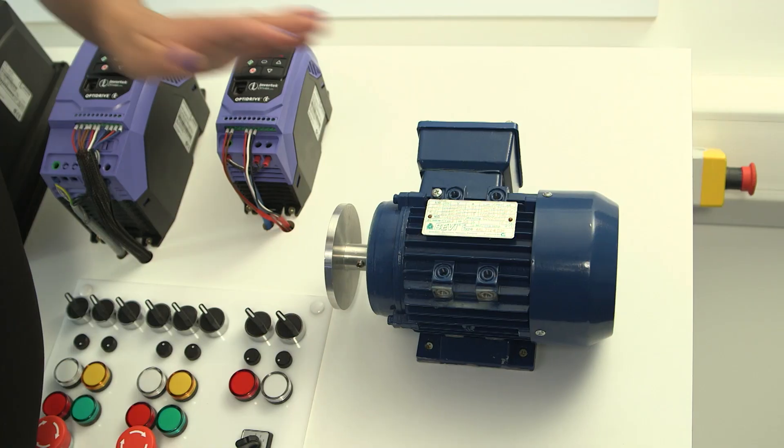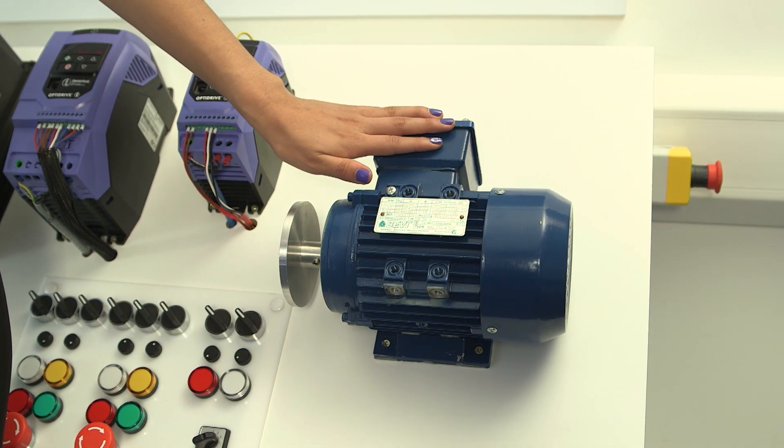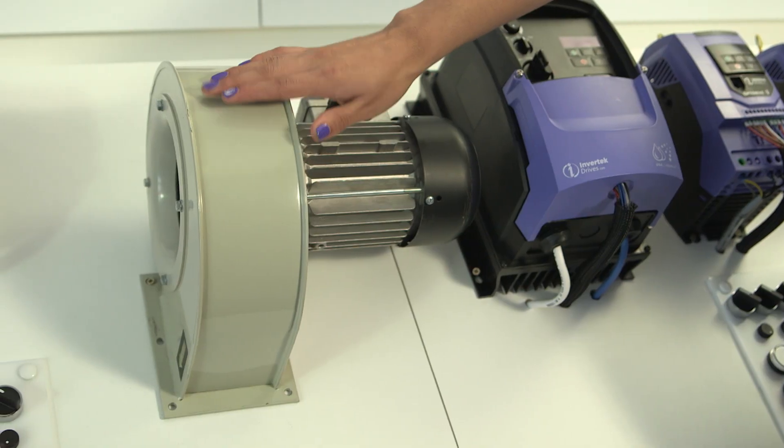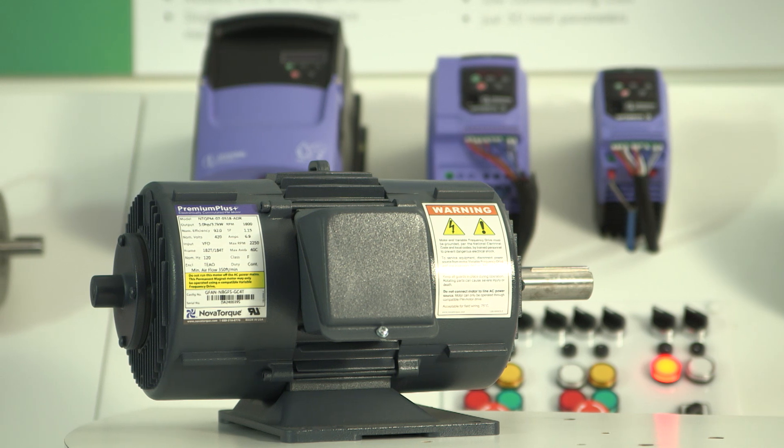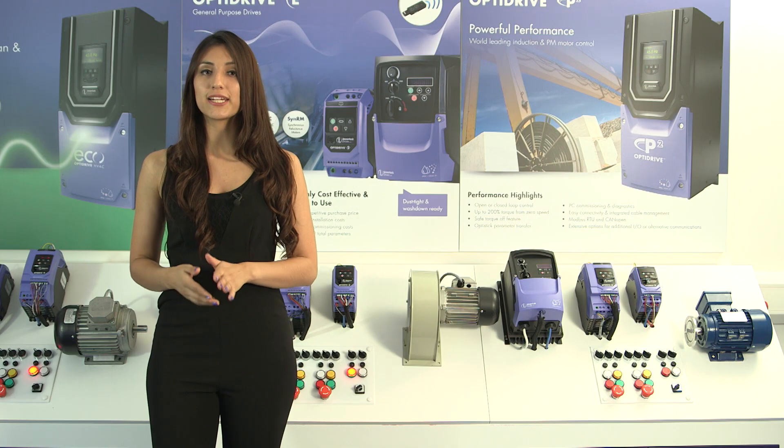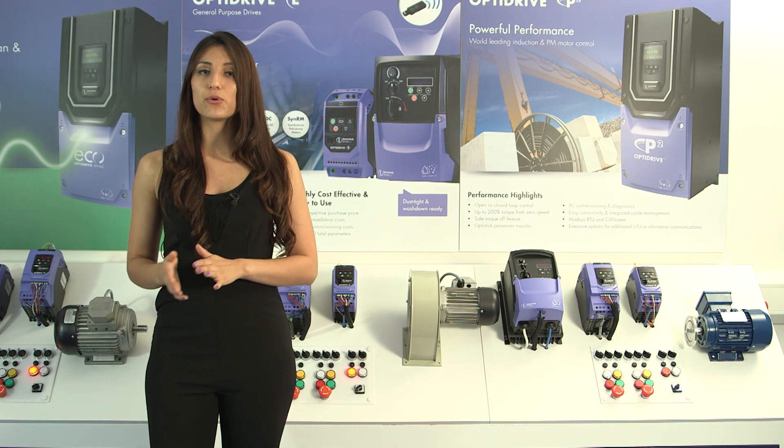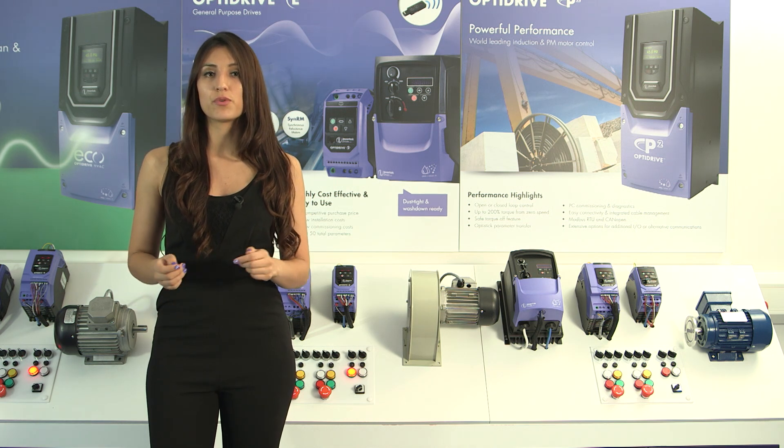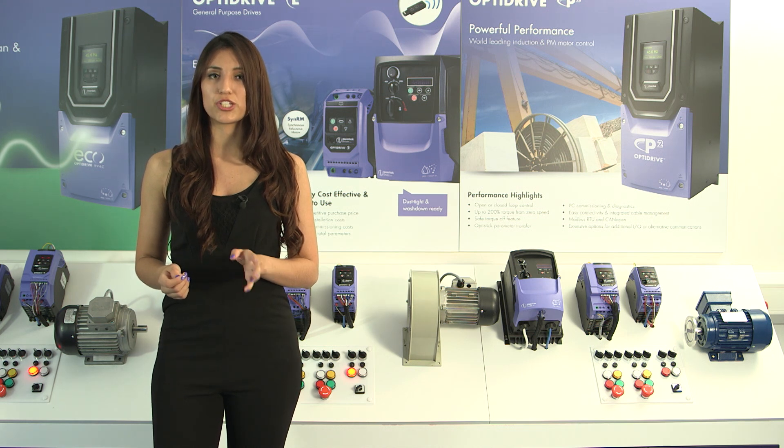It will work with a standard induction motor, of course, but it can be easily set up to operate different types such as brushless DC, synchronous reluctance, and permanent magnet motors. These motors are becoming an attractive solution in many drive applications because they have lower losses than a standard induction motor. They always have to work in vector control and need a different setup procedure.